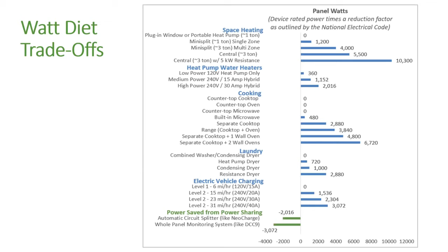And the final 2 at the bottom show examples of automatic circuit sharing systems. The top one is the ACS, like a NeoCharge circuit sharing system, and the bottom one is a whole panel monitoring system like the DCC9 that looks at the total panel load and pauses the EV charger if the total load gets over 80% of the panel rating. So for example, if you were charging your car and cooking with a big party going on and everything happening, and you got up over 80 amps, it would pause the car charger and the party would go on — then later, when the cooking's done, the car resumes charging automatically.